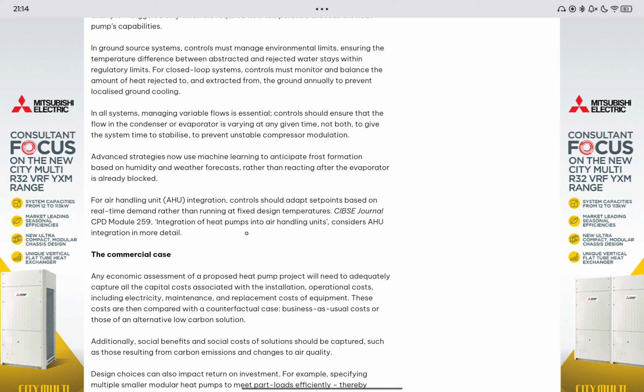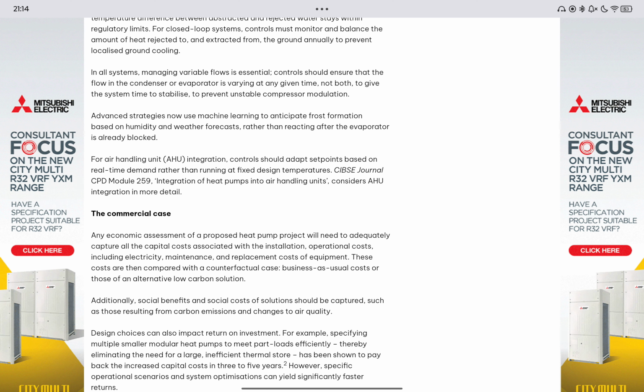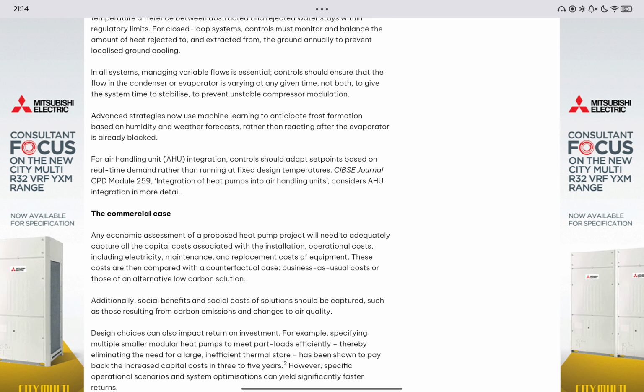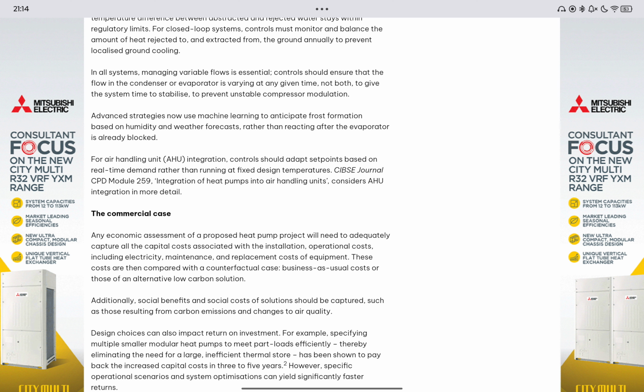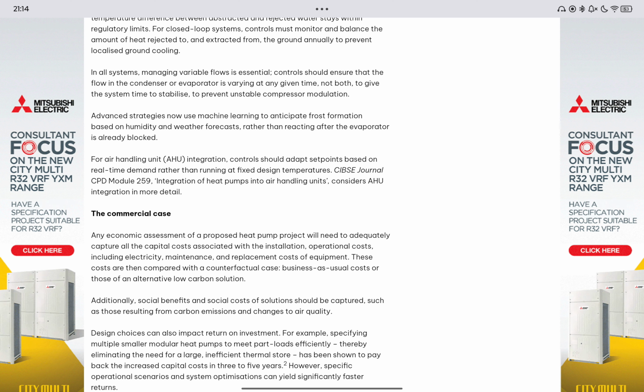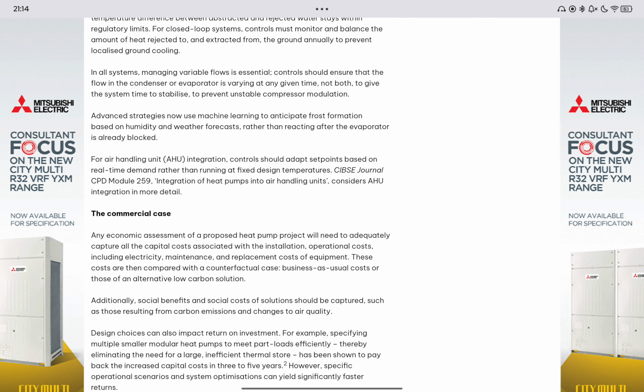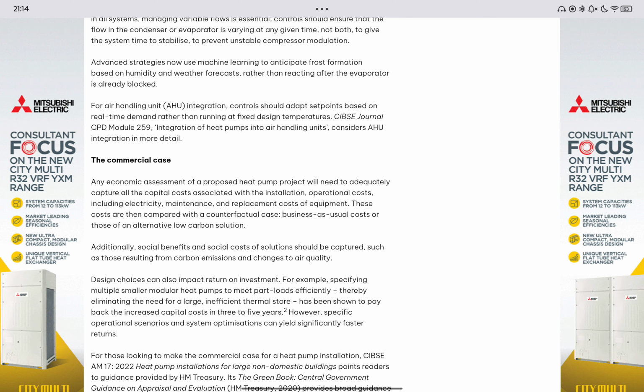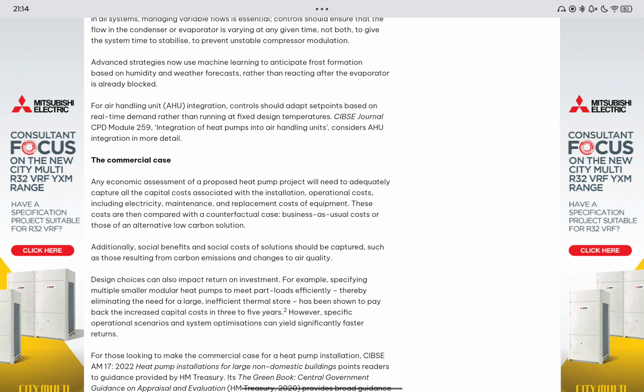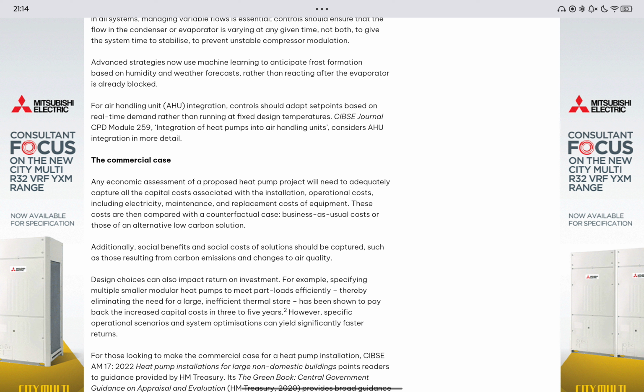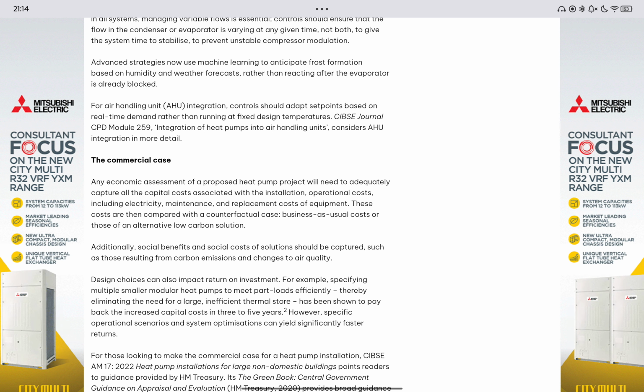In all systems, managing variable flows is essential. Controls should ensure that the flow in the condenser or evaporator is varying at any given time, not both, to give the system time to stabilize, to prevent unstable compressor modulation. Advanced strategies now use machine learning to anticipate frost formation based on humidity and weather forecasts, rather than reacting after the evaporator is already blocked. For air handling unit or AHU integration, control should adapt set points based on real-time demand rather than running at fixed design temperatures.